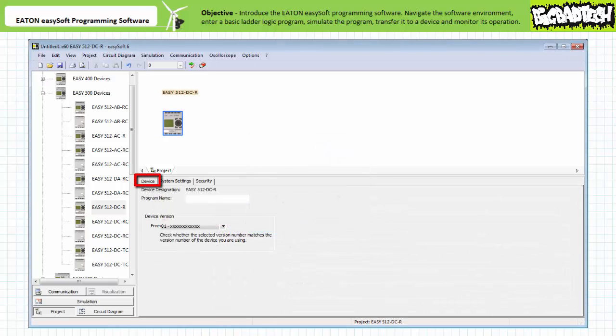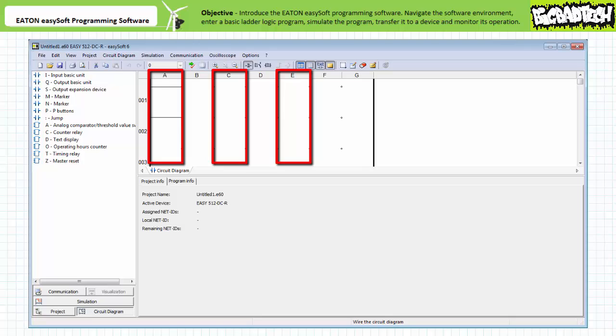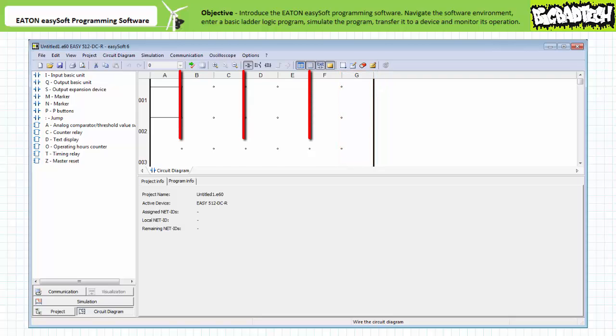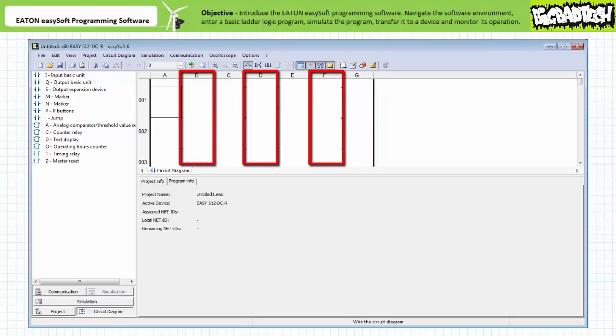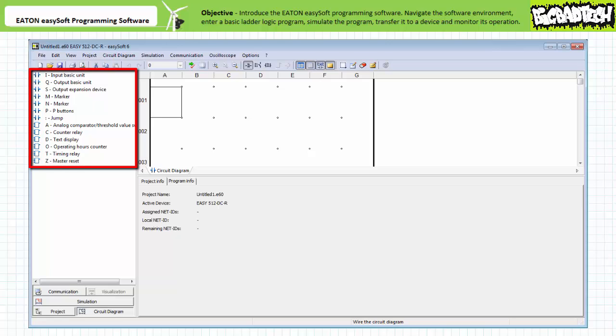In the circuit diagram window, it allows a user to write, save, edit, and manage programs. Note the blank screen is limited to three contact fields on the left — columns A, C, and E — and one coil field on the right, column G. Columns B, D, and F are reserved for wiring. Additionally, the workspace is limited to 128 horizontal rungs as specified by the chosen hardware. Note the left menu features a selection of available contacts and coils.